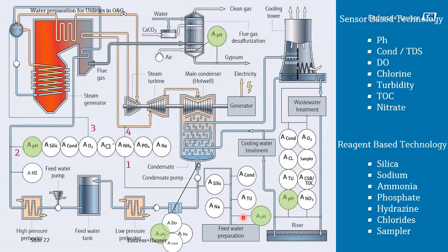So you have the feed water, you want to have an idea about the incoming feed water. Then you go further to the process, to the feed water tanks, then you have a preheater. Here again you want to detect, or monitor, the quality of the boiler feed water, that it meets the criteria before you go into the steam generation. Then you also have the desulfurization.